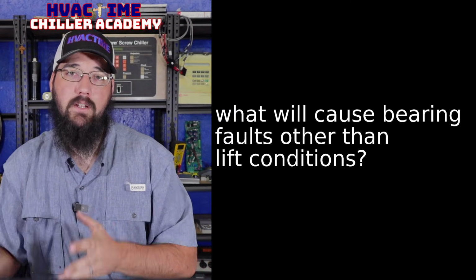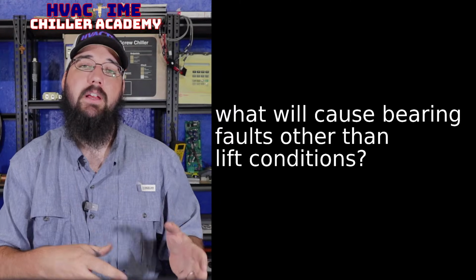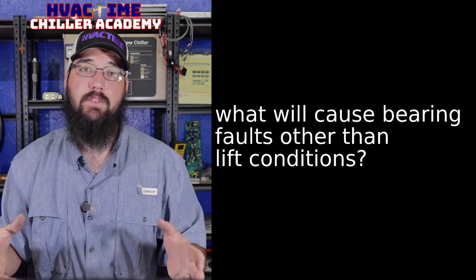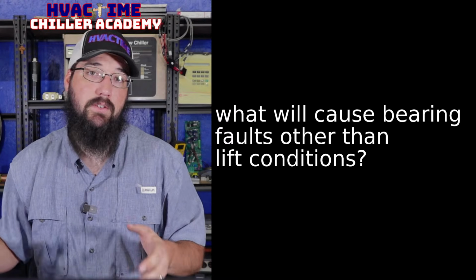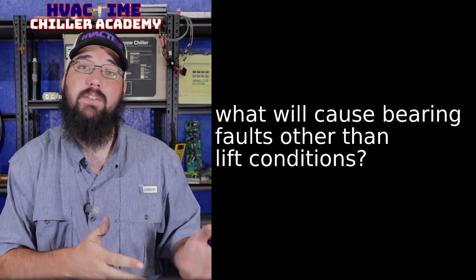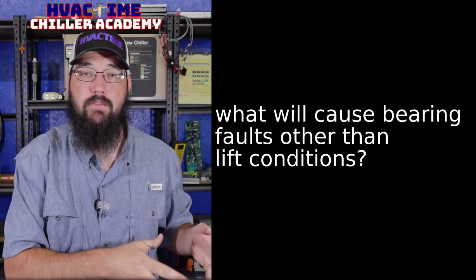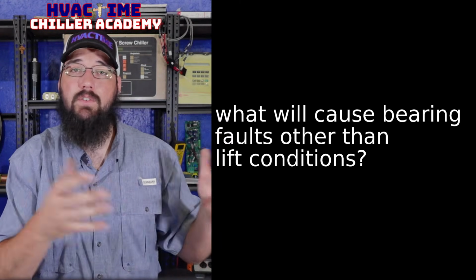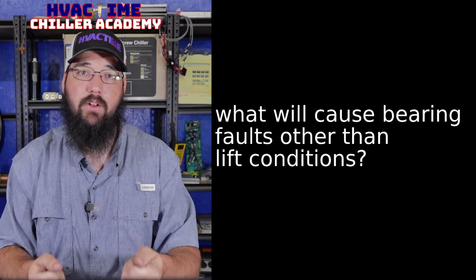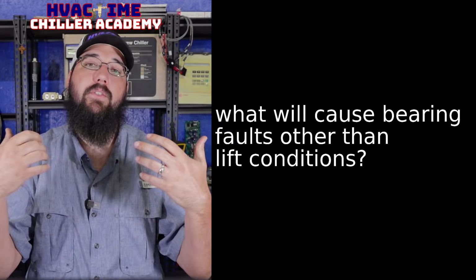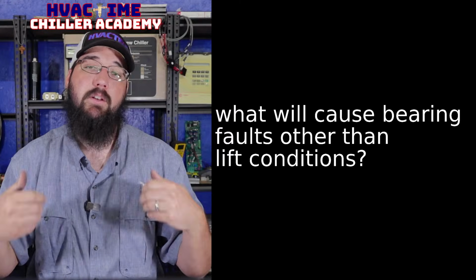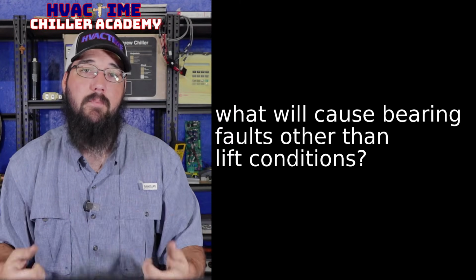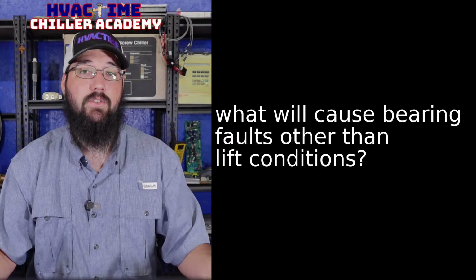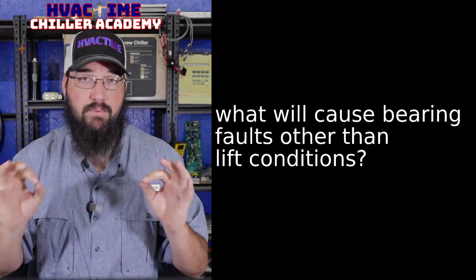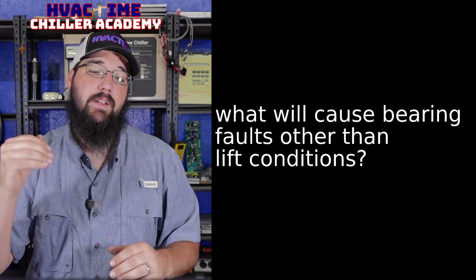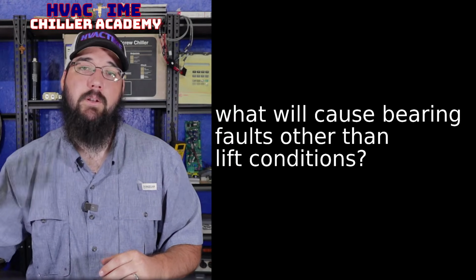If we know it's not a lift issue and we know we're not surging, but we don't want to replace the compressor yet, it makes sense that, okay, well, it could be the inverter. It may make sense to go ahead and do the inverter just in case. Now, obviously, if your bearings test failed whenever you go to check them, then just condemn the bearing. But if the bearings are testing good, typically in my experience, when the bearings test good, they're probably okay. Then that's when I'm worried about the inverter.